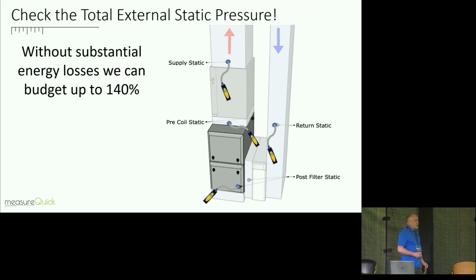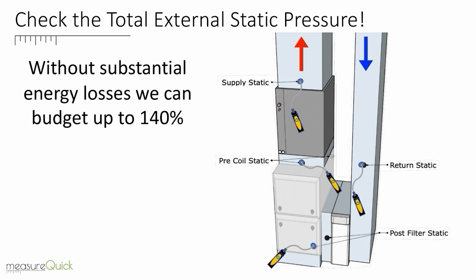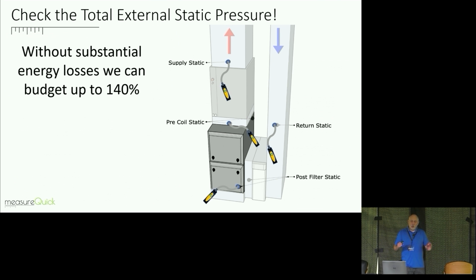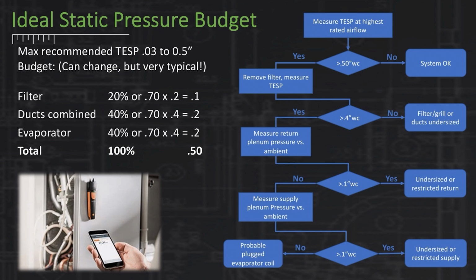So when we're measuring this, okay, and you notice this is sort of grayed out a little bit here, but we want to measure before the coil, and we want to measure in the return. So it's post-filter and pre-coil, because this is a furnace, and the furnace is rated by itself. So anything external to the furnace, we want to include in the measurement. So if you're measuring in your supply air duct and your return air duct, you are in completely the wrong space, because you're missing the pressure drop created by the filter, you're missing the pressure drop created by the coil. All right, so manometers are fairly new to our industry, and you've got to make sure you're making your measurements in the right places.